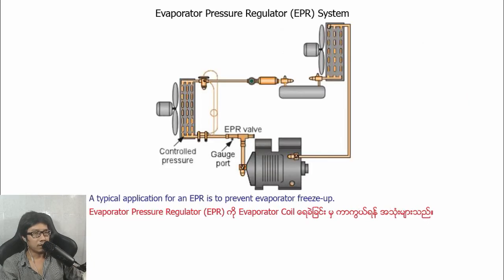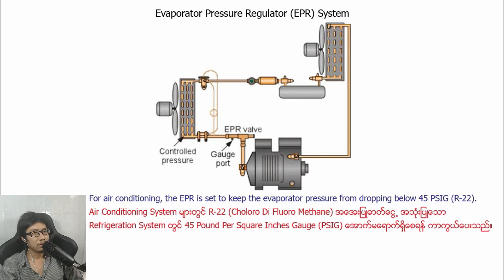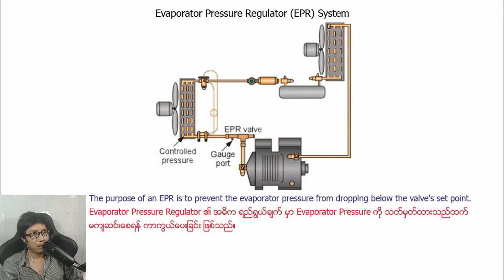Evaporator pressure regulator EPR system. A typical application for an EPR is to prevent evaporator freeze-up. For air conditioning, the EPR is set to keep the evaporator pressure from dropping below 45 psi in an R22 system. The purpose of the EPR is to prevent the evaporator pressure from dropping below the valve's set point.